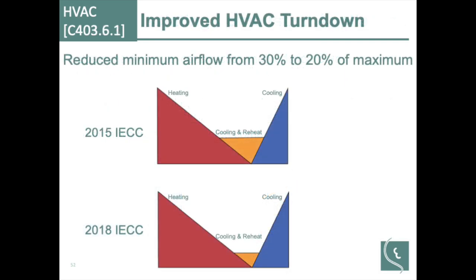For HVAC section 403.6.1, airflow minimums for VAV boxes have been reduced from 30% to 20%. If you're looking at this diagram, it's your reheat and cooling. There's a section there in the middle where you're cooling the air and then having to heat it back up to keep people comfortable in the space. You're cooling the air for humidity control, but then it's too cold to your space, around 65 degrees, if you don't warm it back up. So these reductions to your minimum VAV airflows are just minimizing that simultaneous heating and cooling as much as possible.